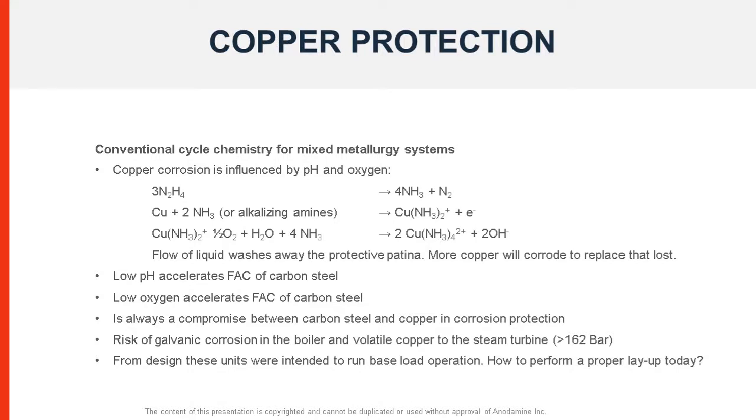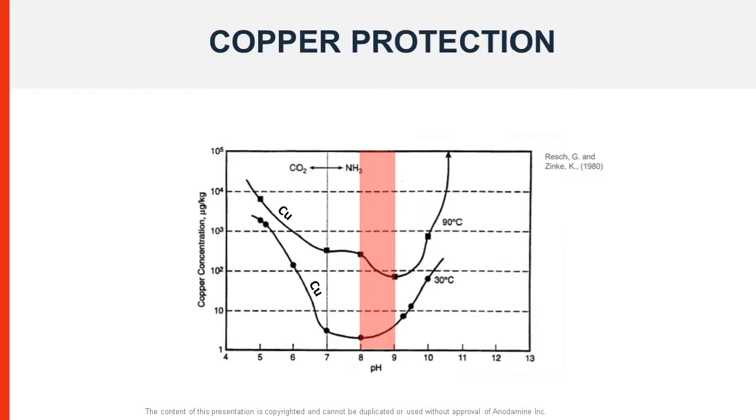So let's go on to the copper protection. If you have alloys of copper in your system and the rest is carbon steel and you have a cycling unit, you have a challenge when using conventional chemistry. It is virtually impossible to please the copper and the carbon steel at the same time. And this is because...